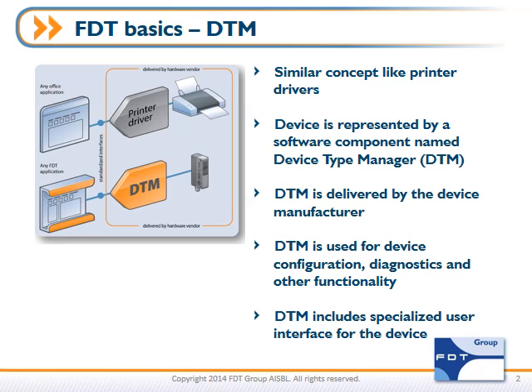Let's start with some of the basics of the FDT standard. The first part is called the DTM, or Device Type Manager. This is similar in concept to a driver for a printer in a Windows application. The device in the factory automation environment is represented by this DTM component. The DTM is typically delivered by the device manufacturer, and it's used for configuration, diagnostics, asset management, calibration, and a host of other functionality. The DTM includes a very rich graphical interface that allows the device manufacturer to represent their product in the best light possible.